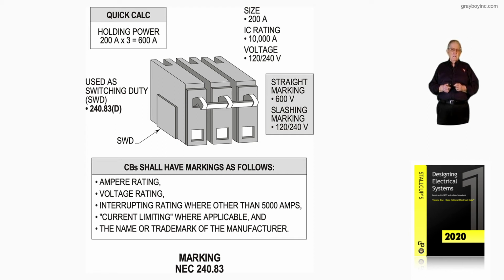Now the other markings is below the circuit breaker, and it's boxed in information. It says circuit breaker should have markings as follows: amperage rating, voltage rating, and any type of interrupting rating. Now basically, if a circuit breaker is not marked, it's only good for 5,000. But this one was marked 10,000, maybe 22,000, 30,000, 40,000, 50,000, 60,000. But it'll be marked, and then you know what amount of short circuit current, ground faults, say available short circuit current is capable of interrupting.